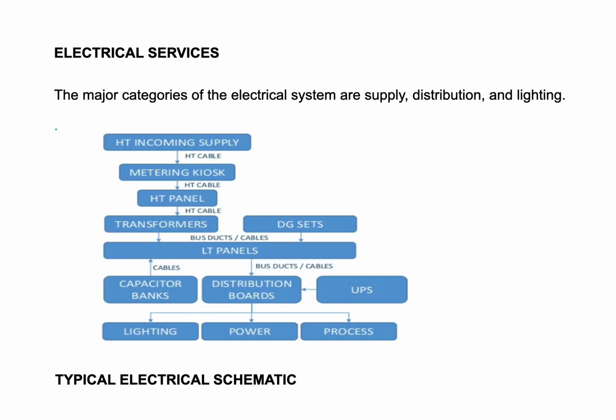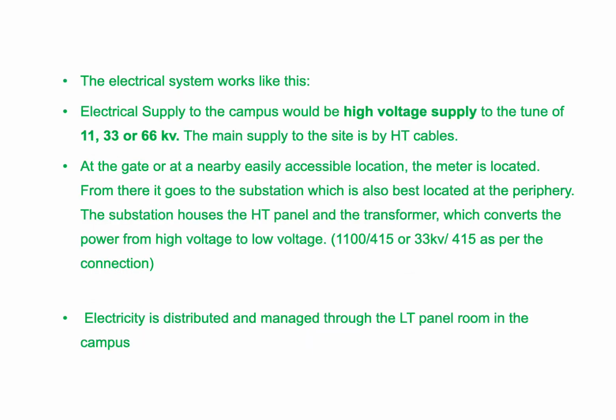The major categories of the electrical system are supply, distribution, and lighting. For electrical system designs too, the design parameters are set in accordance with the codes. These are the minimum requirements that must be met. The electrical system works like this. Electrical supply to the campus would be in high voltage supply to the tune of 11, 33 or 66 kV. The main supply to the site is by HT cables.